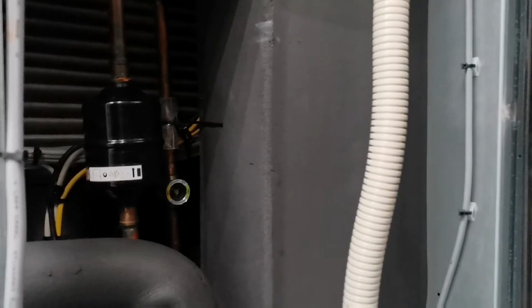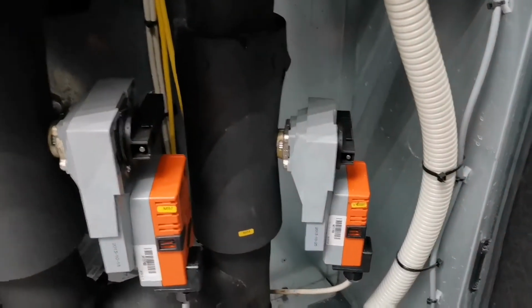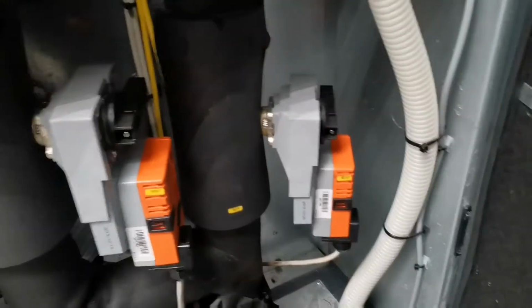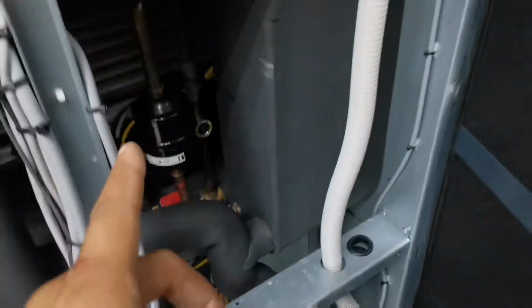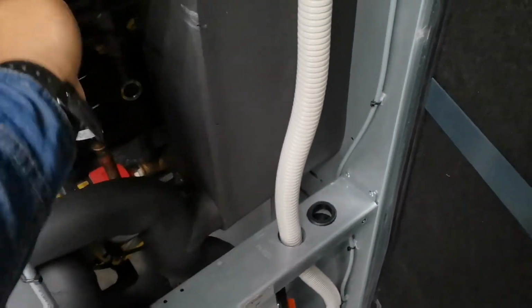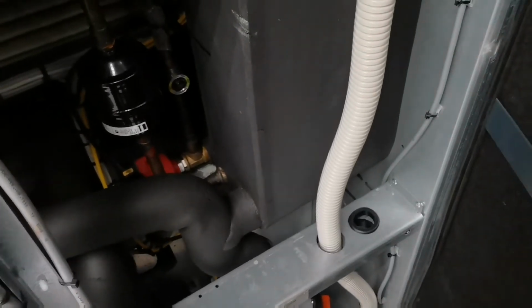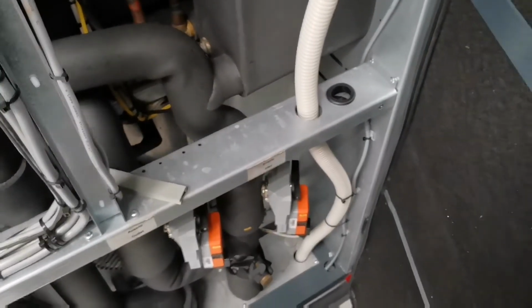So we should have, there's just a delay on the compressor startup, which was extended because this system uses a dry cooler. So there are valves that need to open, since we have a water heat exchanger right here, which is basically our condenser. Water is 60% more efficient at removing heat than air. That's why we can have the heat exchanger compact and a lot smaller. So we're just waiting for the delay, and then you'll see one of these valves will open, allowing water to start flowing through the heat exchanger, and then the compressor will start up. So there is a delay time set for that, so we can ensure that we don't get any HP alarms prematurely. So yeah, I'll give you guys the footage once the compressor starts.